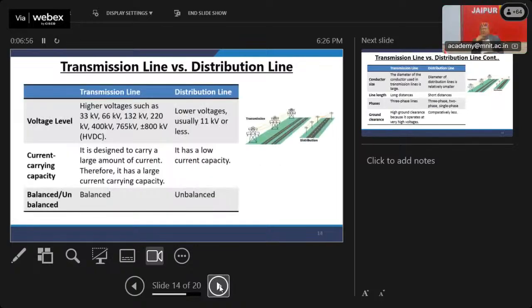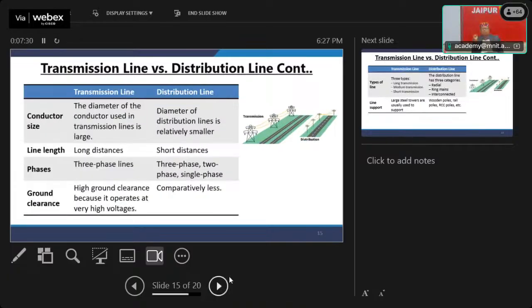Next, please. Now, if I compare transmission lines versus distribution lines, in voltage level you could see the differences: 33, 66, 132, 220, 400, 765, plus or minus 800 kV, and the distribution network is usually 11 kV. Current carrying capacity is low in the distribution system, and it is large in the transmission system. The system is normally balanced in the transmission system, and it is 100% unbalanced in the distribution system.